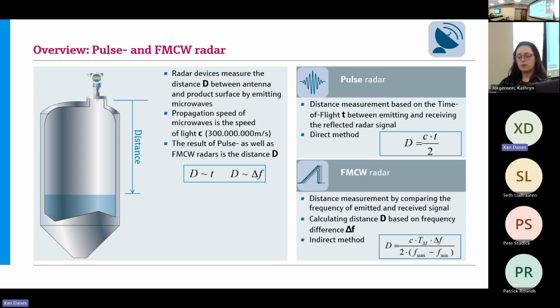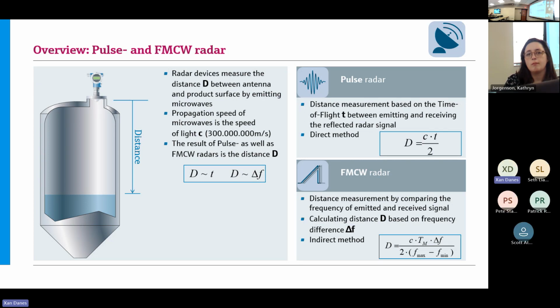With a frequency modulated continuous wave radar, I'm not really measuring time anymore within the device. These radars work by constantly sending a frequency, and at the same time constantly receiving a frequency, so I'm calculating distance based on the frequency difference. This is technically a less direct, or indirect, method to measure level compared to a pulse-based radar.